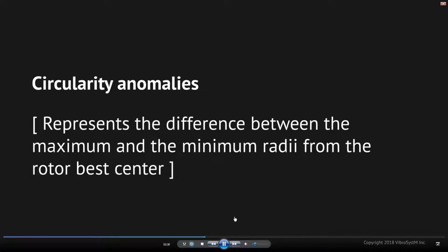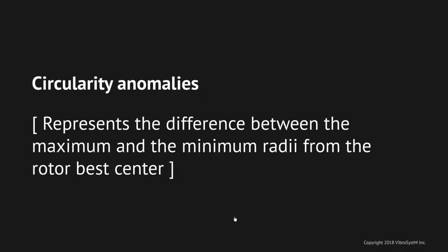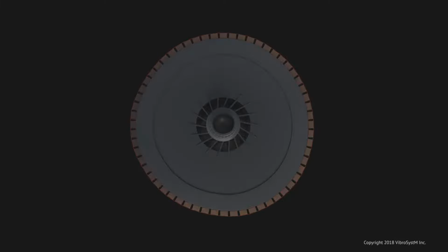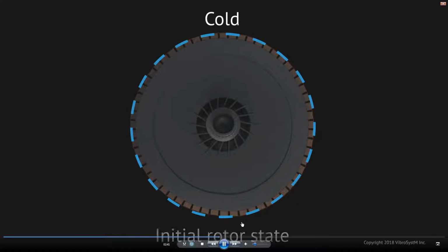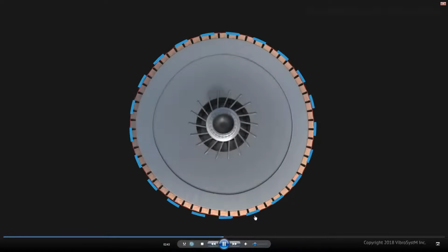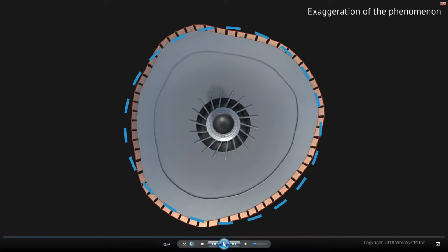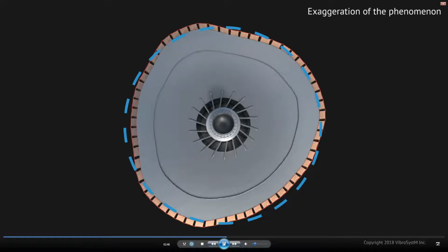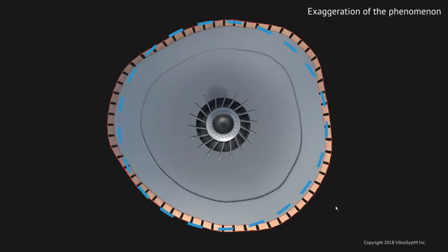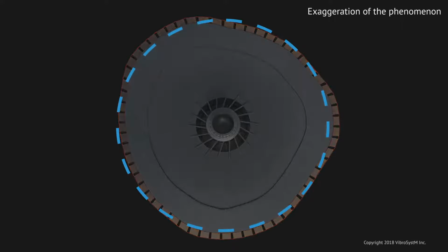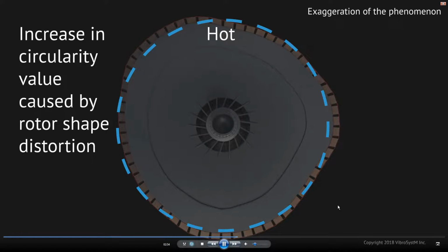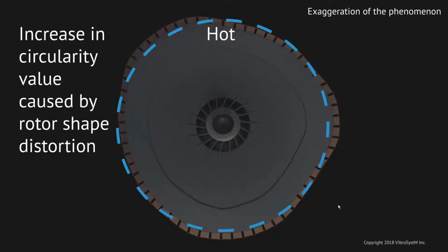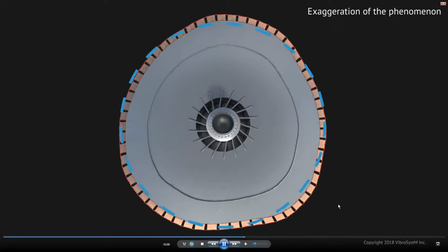Circularity anomalies, well, these represent the difference between the maximum and the minimum radii from the rotor best center. Okay, so in this case, we have the initial rotor state, and eventually we'll have distortions, but at different locations, not just one location, but different locations. And that looks like a real rotor. Maybe surprisingly to some, but that looks like a real rotor. So the increase in circularity is caused by rotor shape distortion. The idea is to find out how much distortion and is it acceptable.